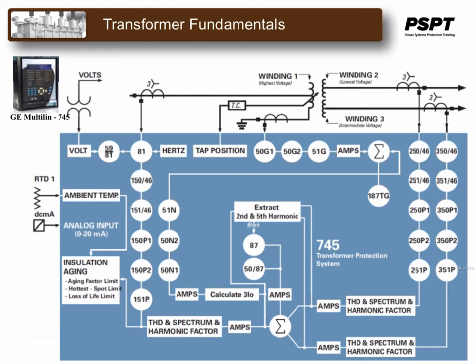This is the functional diagram for the relay. It may appear a little bit confusing because each one of the function numbers associated with one of the individual three windings of the power transformer is prefixed with a 1, 2, or 3, depending on the winding that it's associated with. For example, for winding 1, the prefix on the function numbers is 1. For winding 2, the prefix number is 2. And for winding 3, the prefix number is 3. So if you just remove those winding numbers, it becomes a little bit more obvious. The standard function numbers are as listed here on the diagram. As you can see, it pretty well covers the entire spectrum of protection that's required for the transformer, and then some.